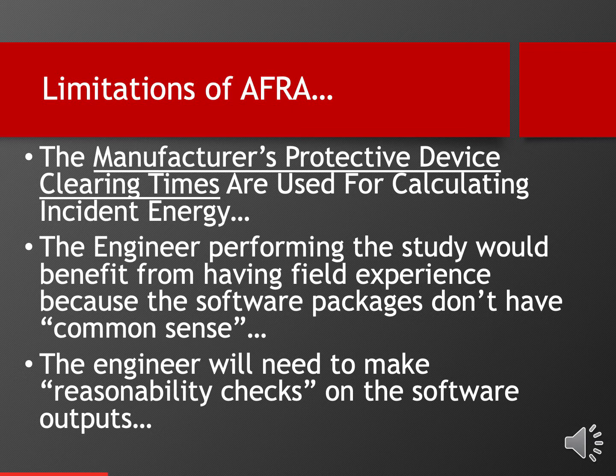So some of you may be working in facilities like steel mills that may be 100 years old. Some of the equipment could easily be 50 or 60 years old in those environments. And of course, in those situations, if you don't have an extremely aggressive maintenance program, the chances of a circuit breaker that's been in the closed position for, say, 20 years, operating at nameplate speeds is pretty remote. So point number one has to do with electrical maintenance, and I cannot overstress the importance of that maintenance program, because if those breakers are even a little bit sticky and they open up slightly slower, you'll notice the incident energy goes up exponentially.